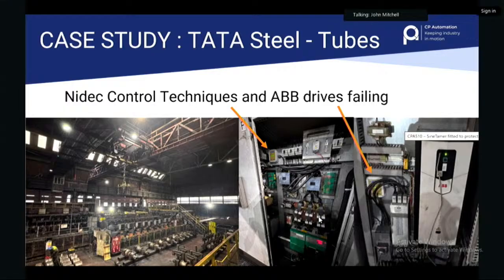We investigated, we measured, we saw the spikes, and immediately suggested sine tamers. We installed 7 across the site, one per panel for a bank of drives. They haven't had a problem since - it's been over a year, and they haven't had a single failure.